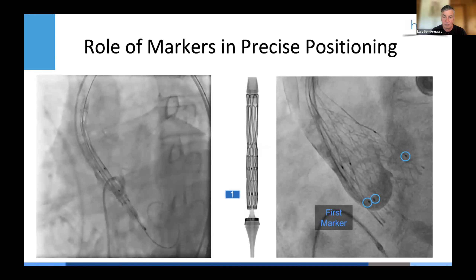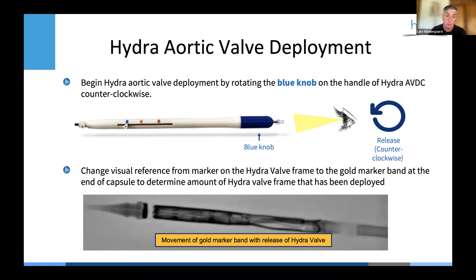And again, it's a very simple handle. You just have a blue knob here. You do a counterclockwise rotation. That leads to unsheathing of the device very slowly, so you have time to correct and optimize the position. It's also illustrated here that the valve is slowly coming out. You can pause at any time and adjust the position.